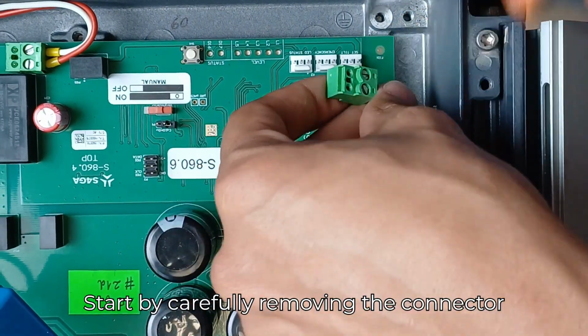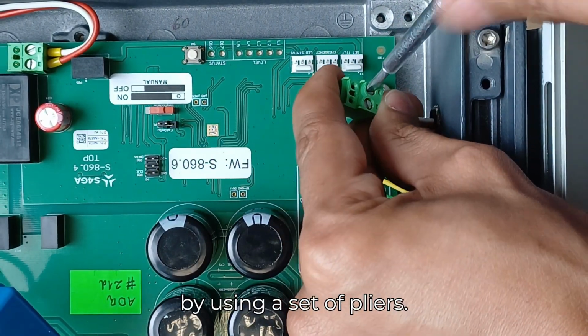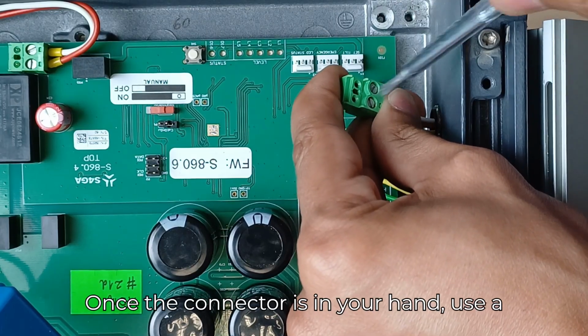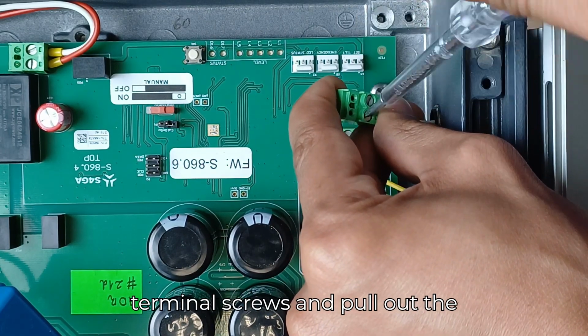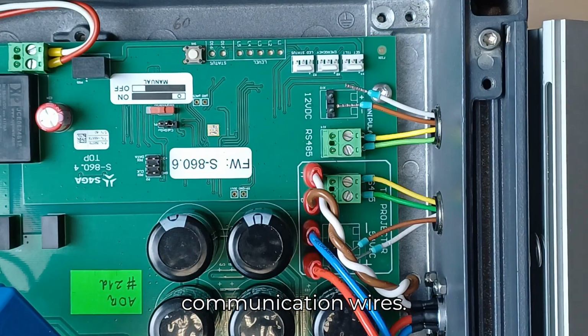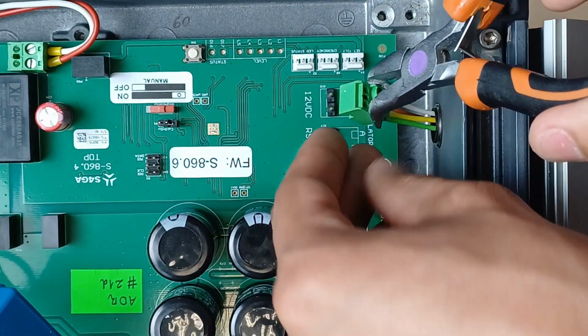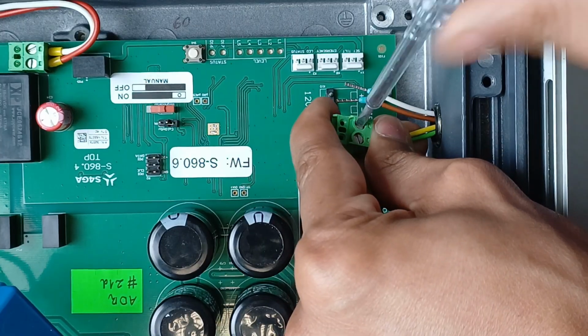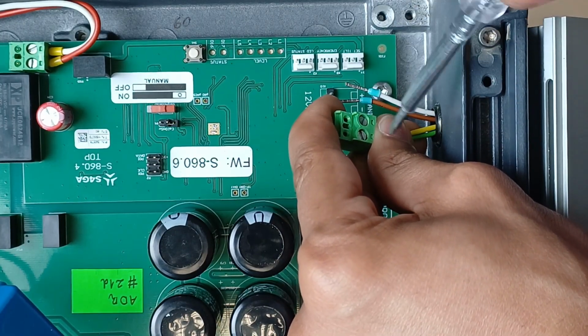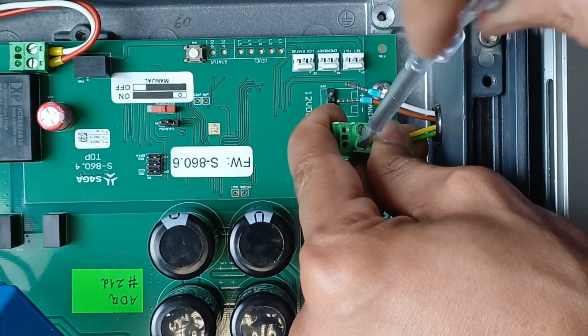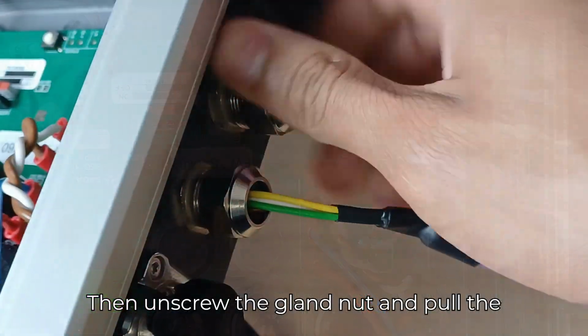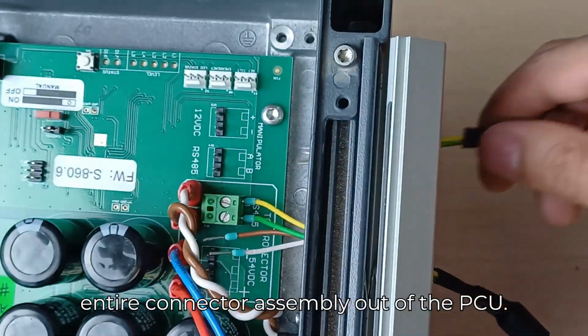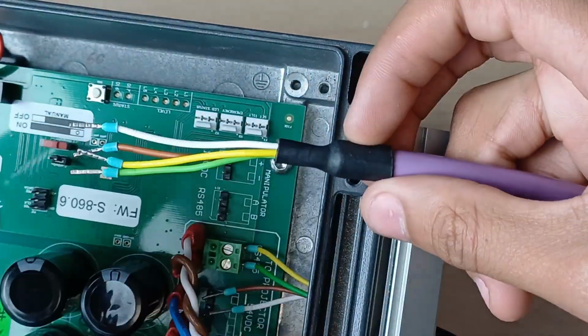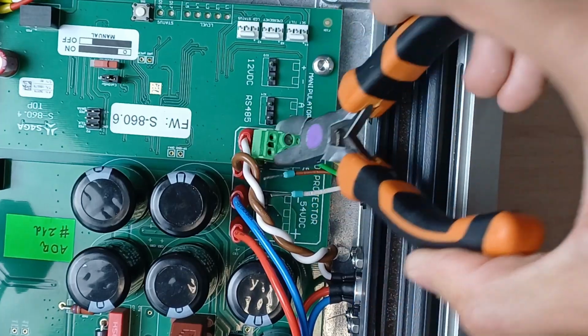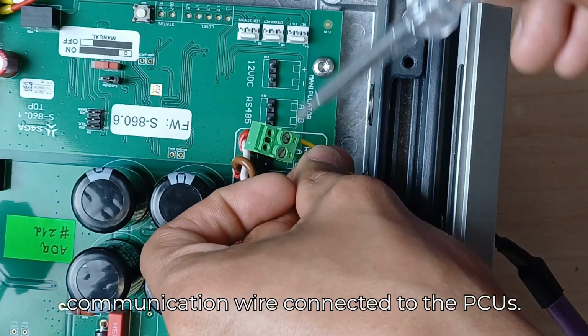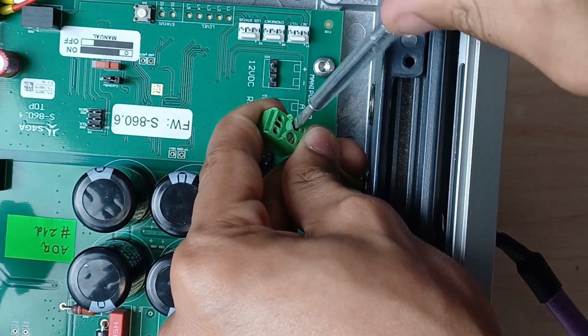Start by carefully removing the connector by using a set of pliers. Once the connector is in your hand, use a flathead screwdriver to loosen the terminal screws and pull out the communication wires. Then, unscrew the gland nut and pull the entire connector assembly out of the PCU. Repeat this process for every communication wire connected to the PCUs.